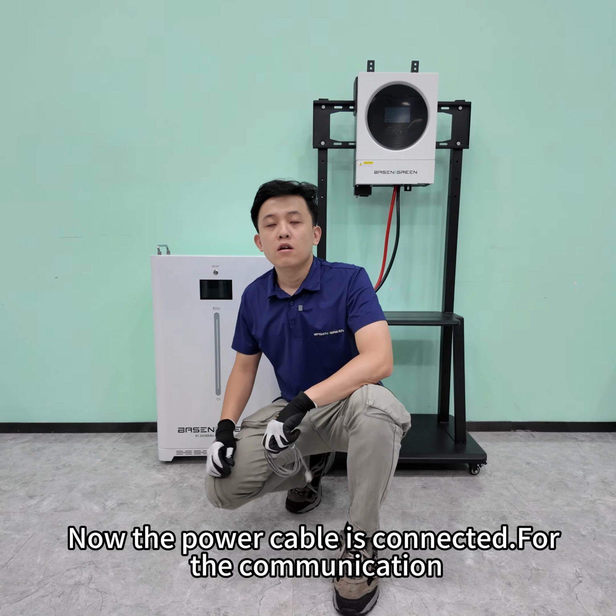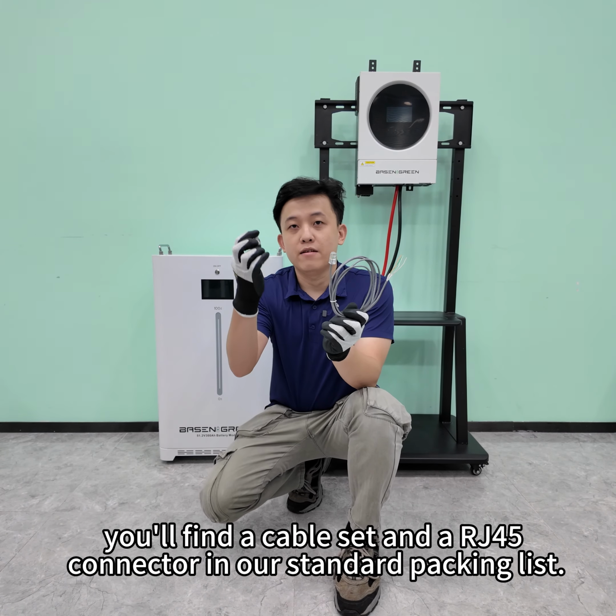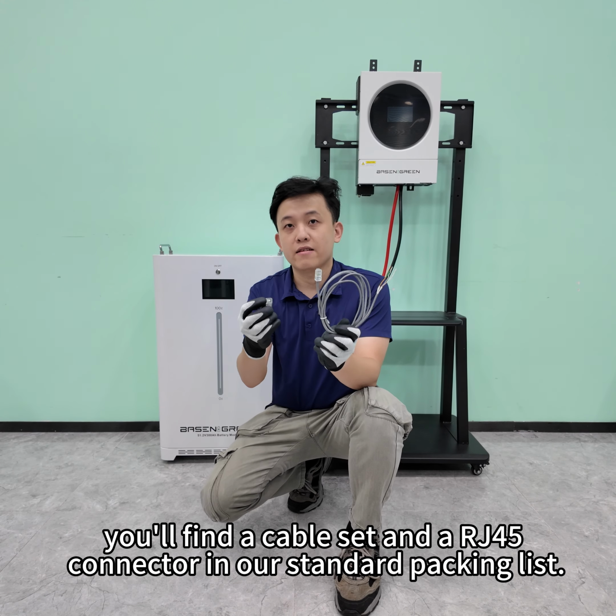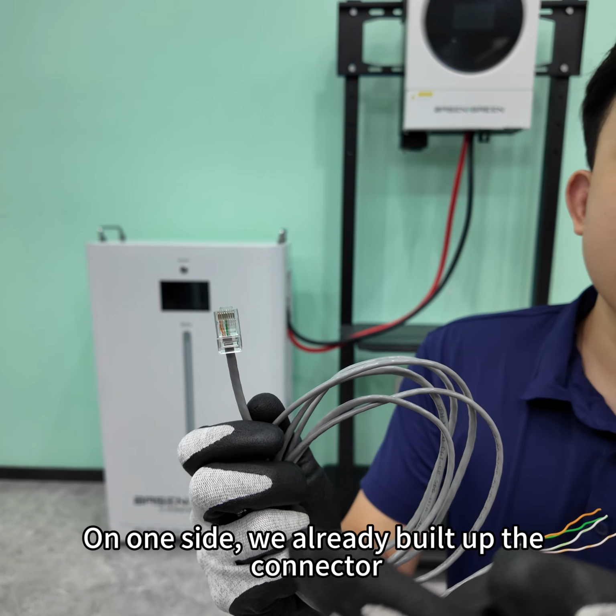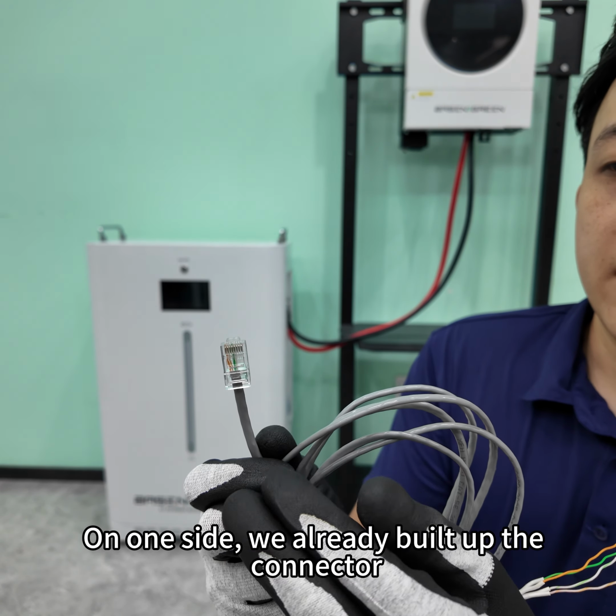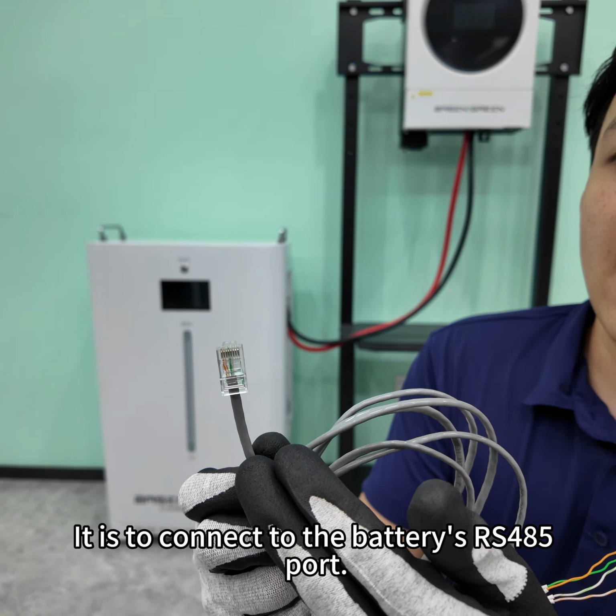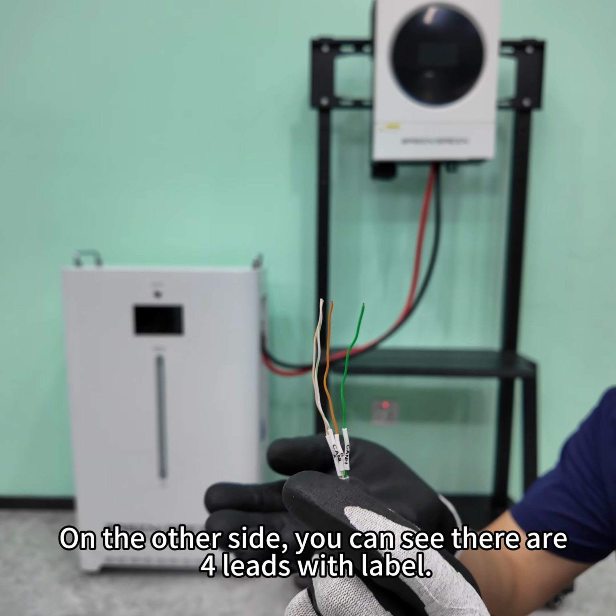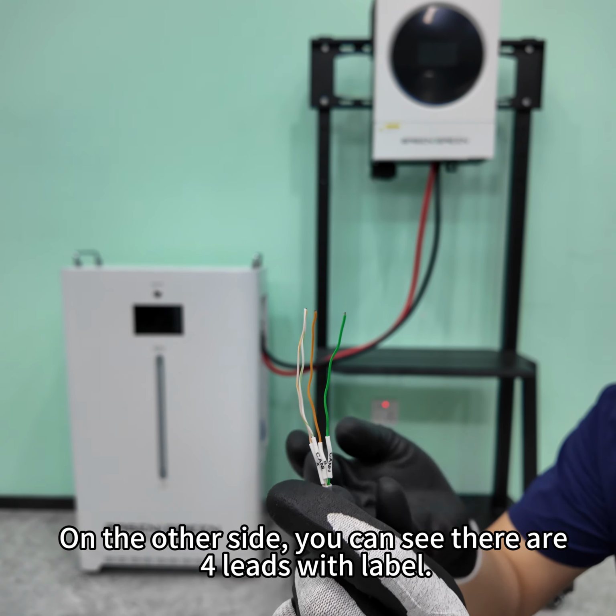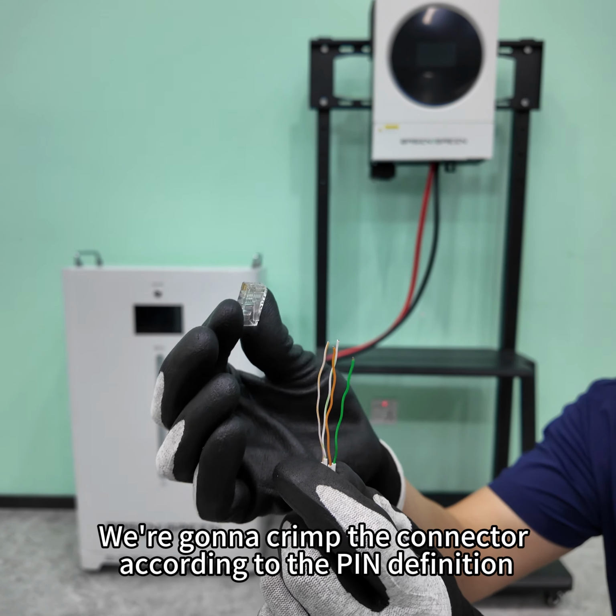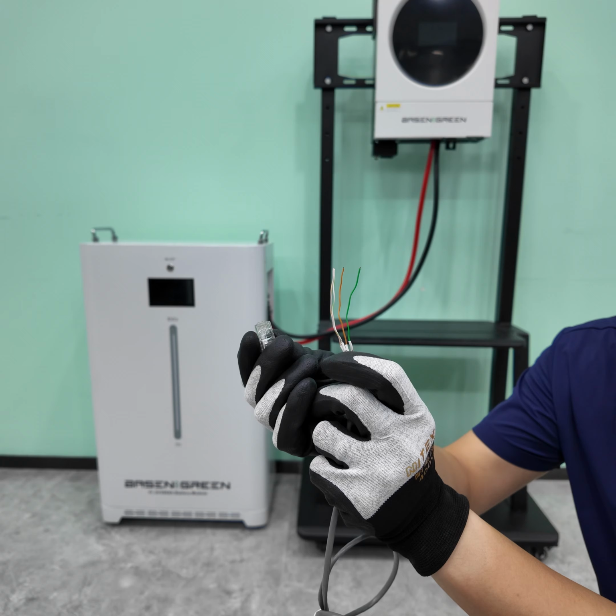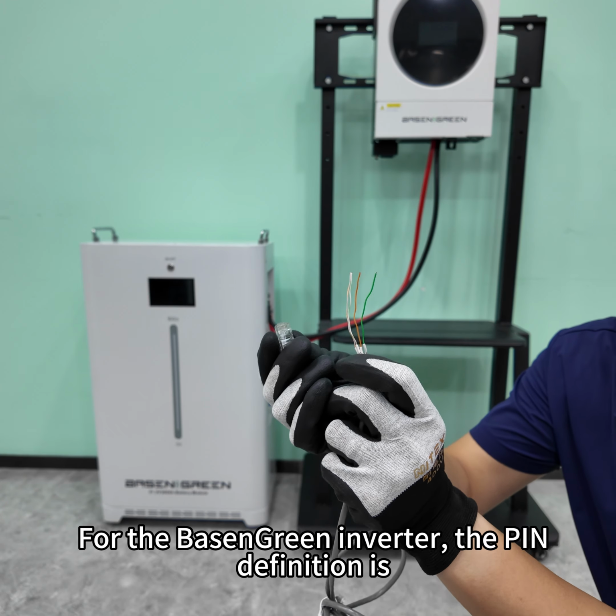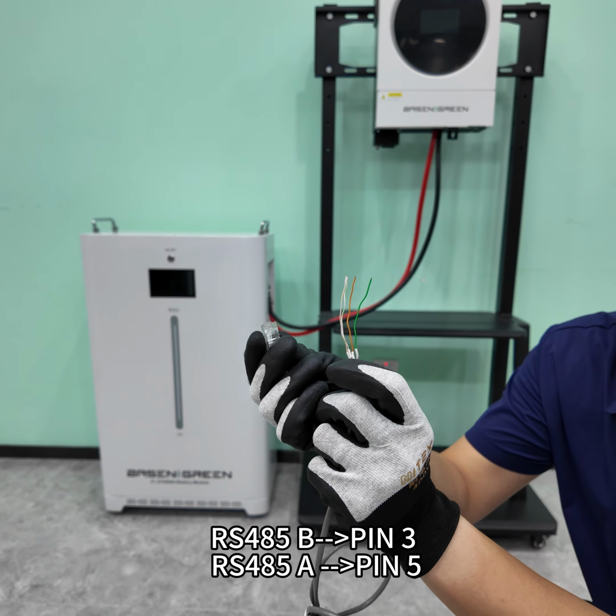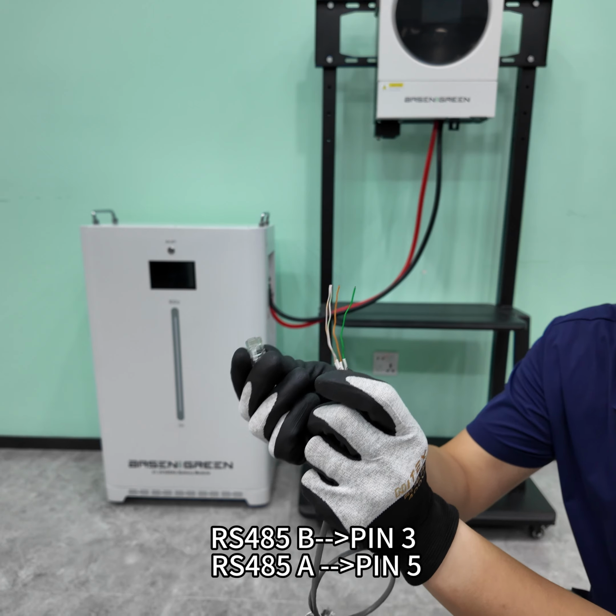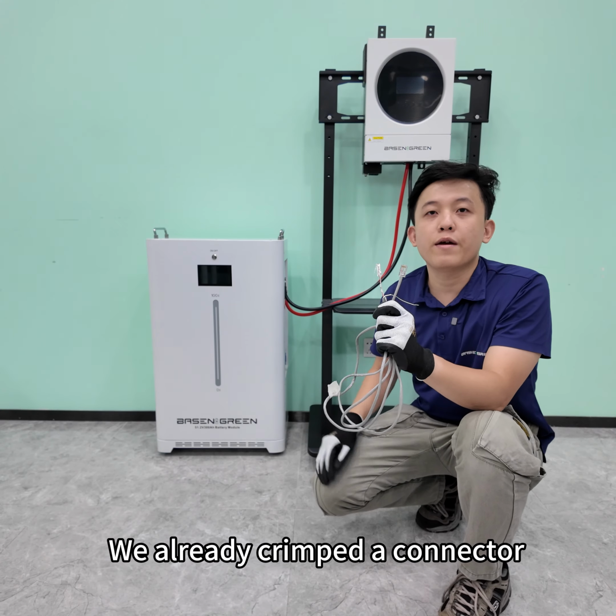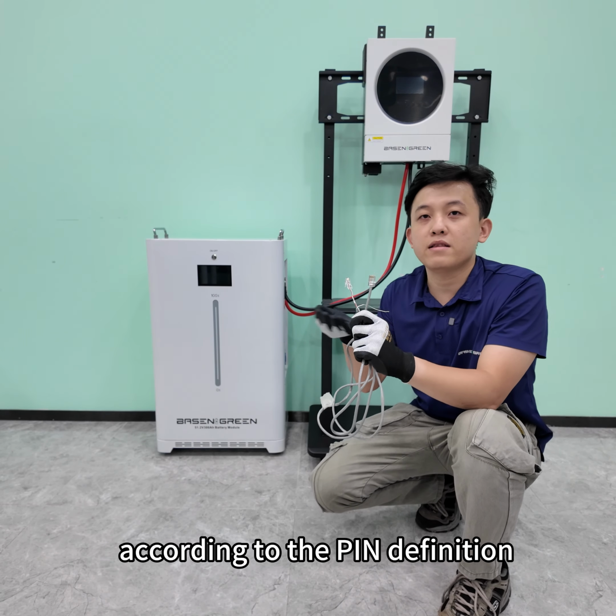For the communication, you'll find a cable set and an RJ45 connector in our standard packing list as well. On one side we already built the connector to connect to the battery's RS485 port. On the other side you can see there are 4 wires with labels. We're going to crimp the connector according to the pin definition. For the BasenGreen inverter, the pin definition is RS485B to pin 3 and RS485A to pin 5. We already created the connector according to this pin definition.